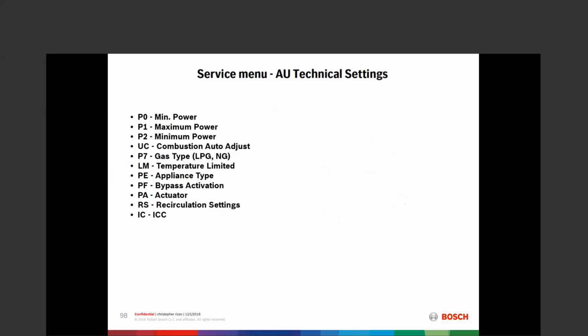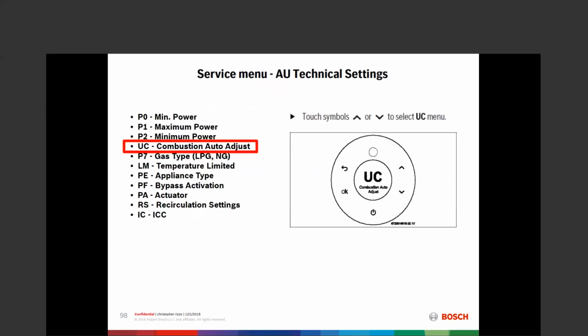It also now gives us access to UC, which is combustion auto adjust. Combustion auto adjust is where the unit's going to go through a 9-step process to ensure the combustion efficiency. What it's basically doing is the process that a technician would do with a combustion analyzer. The electronics on the unit, the software on the unit are doing that for us using the ionization current, the flame sensor, to evaluate flame quality.